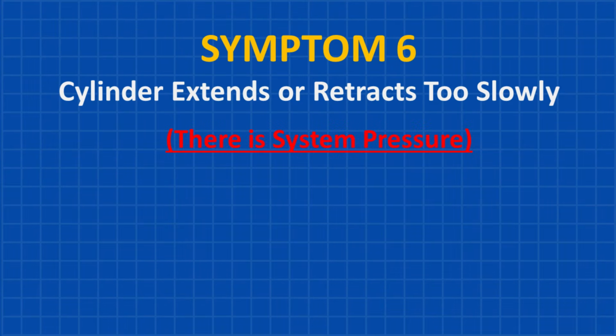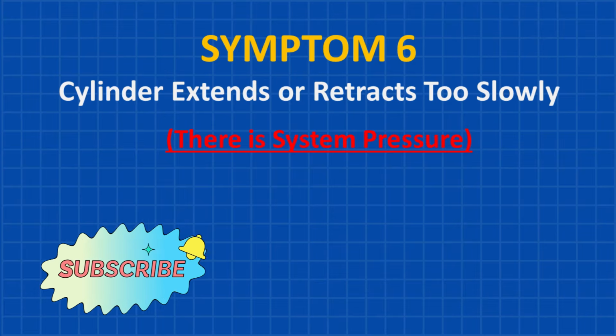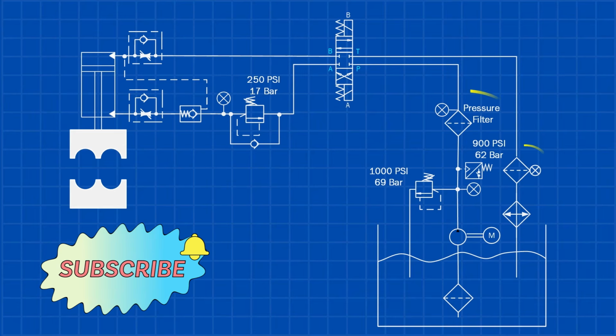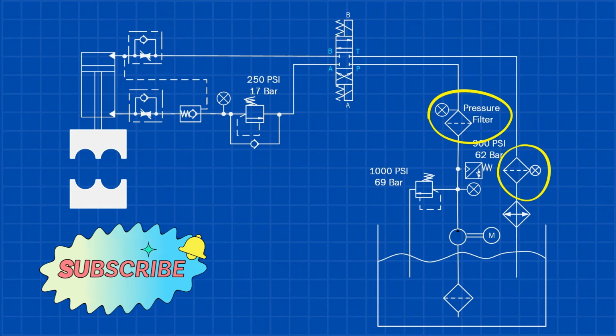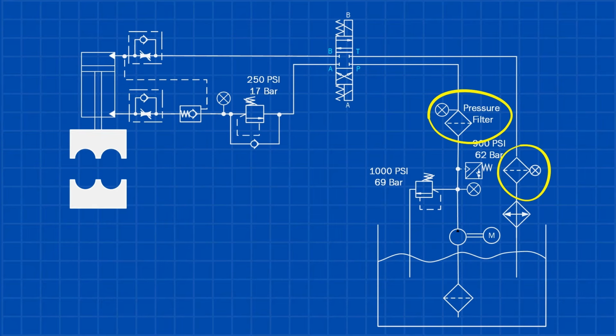Symptom 6. Cylinder extends or retracts too slowly, and we have system pressure. If a pressure or return filter gets clogged, it can slow down the movement in both directions. In this case, you need to check which filter is dirty and replace it. Not all pressure and return filters have a bypass, especially in systems where contamination control is critical. This is because allowing unfiltered oil to pass through can damage sensitive components. However, all filters should have a contamination indicator or switch to alert you when they're dirty.